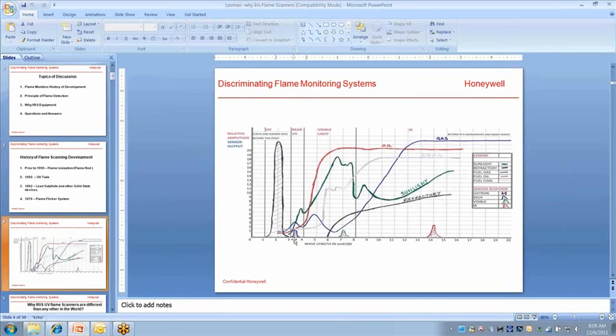The solid state sensors are great. If you have oil and coal, I would have no hesitation to use sensors that respond in UV, near UV, visible light, or even IR. We have used the IR sensors in this region on oil and coal in so many places with great success.